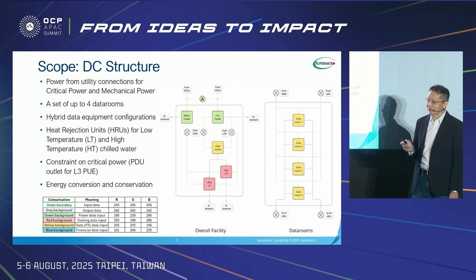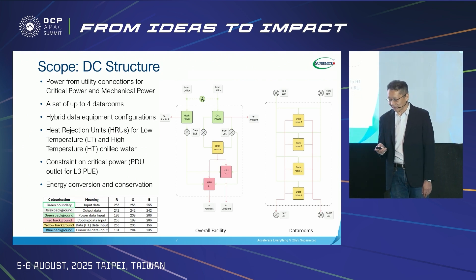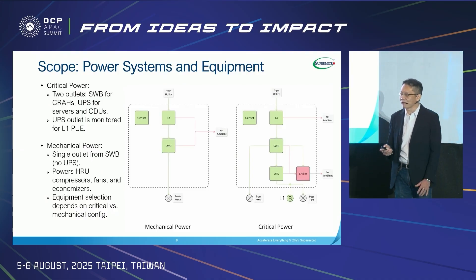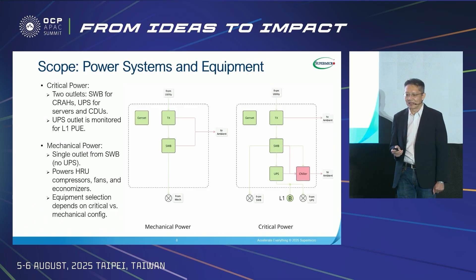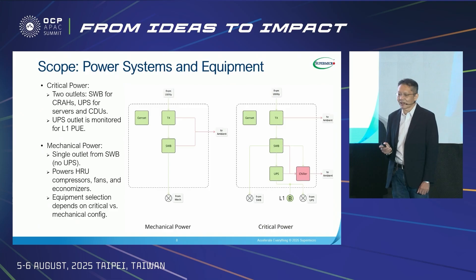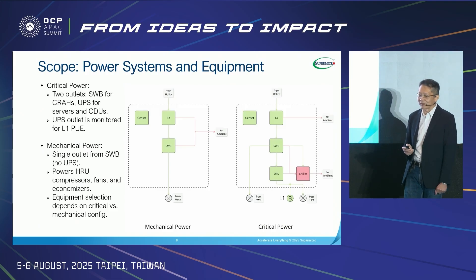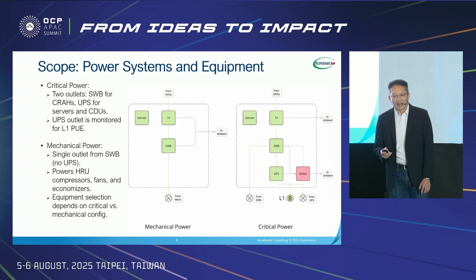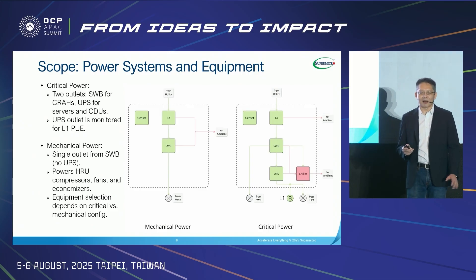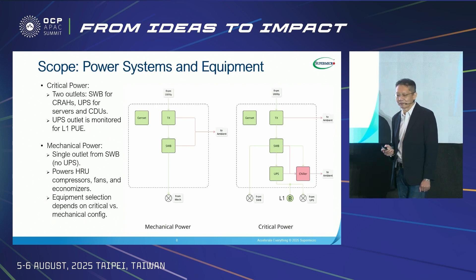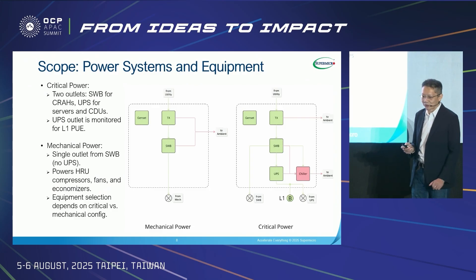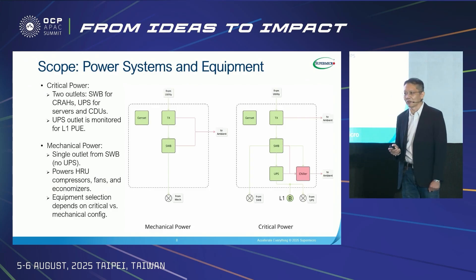This table shows the purpose of each cell in the worksheets along with color reference. The critical power has two power outlets: one from the main switchboard and one from the UPS. The UPS output is for air cooling, known as CRAC. The UPS outlet is reported for L1 PUE assessment. The mechanical power has a single outlet from the switchboard and feeds the HRU compressors, fan sets, and economizers. Power equipment is selected based on critical and mechanical power configurations.